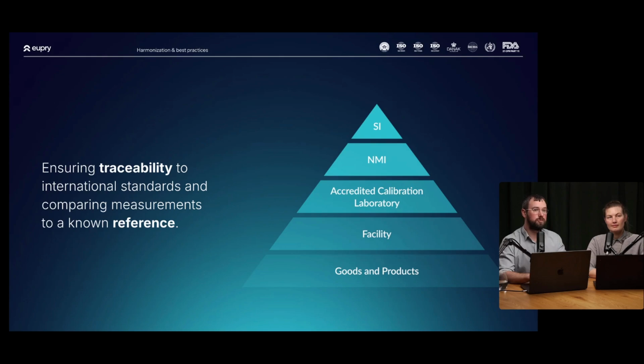In most countries, you have one, and in some several, national metrology institutes, which are the best to calibrate a certain parameter, be it the kilogram, the second, or the Kelvin, as in temperature that we're going to talk about today. Through accredited calibration laboratories, they get their equipment or references calibrated at the NMIs, and then they calibrate equipment used at the facility and then down to the goods and products. So it's really through an unbroken chain of calibrations, all the way up to the realization of the SI units, that we have traceability to international standards.